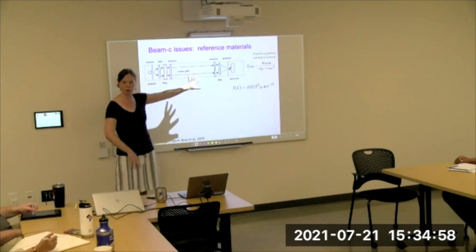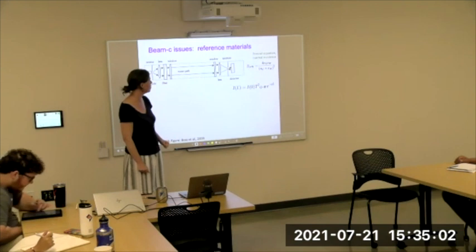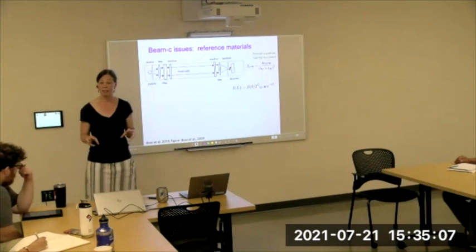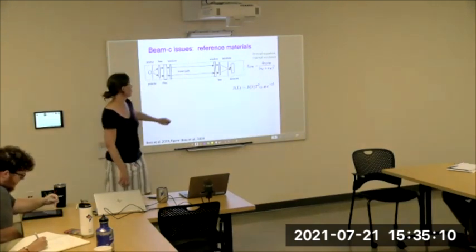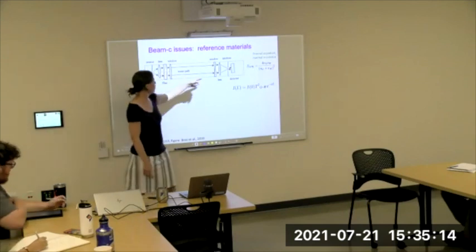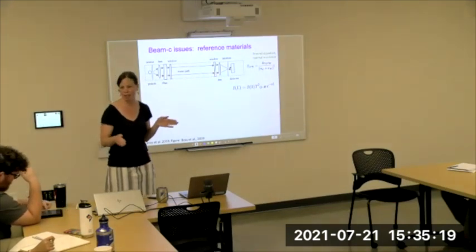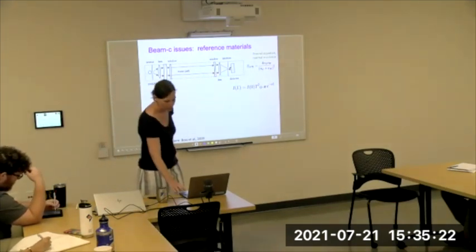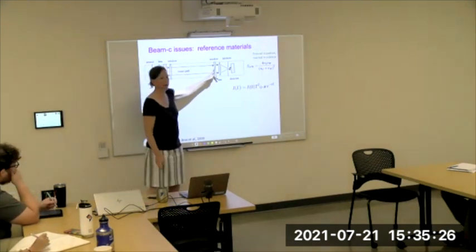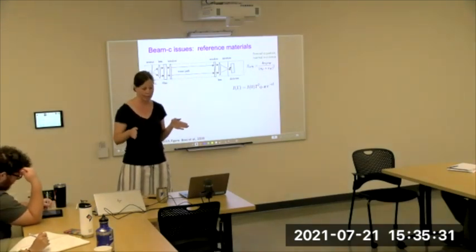So there's a solution for just the case where the light is coming in at a normal angle. It depends on the degree of mismatch between those refractive indices. When you're going from the air to the window and from the window to the air, it doesn't matter what's in your fluid volume, what your sample water is. But when you're going from the glass to the water, and then from the water back to the glass, both times you lose a little bit of light because of that refractive index change.